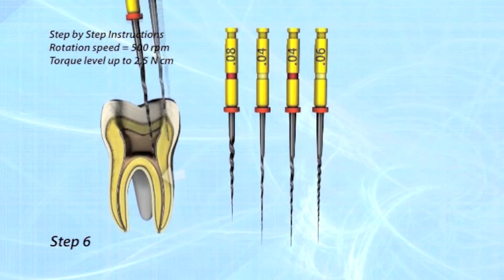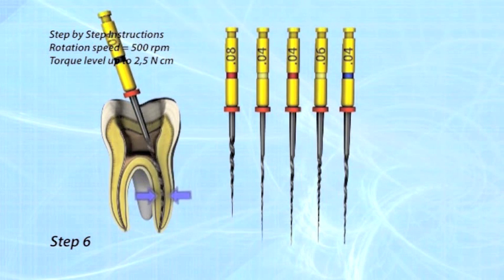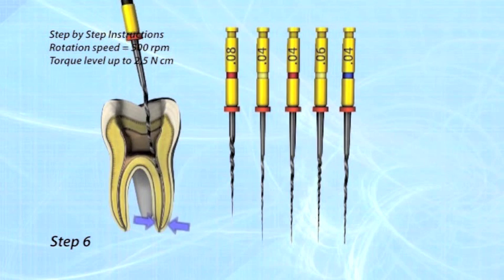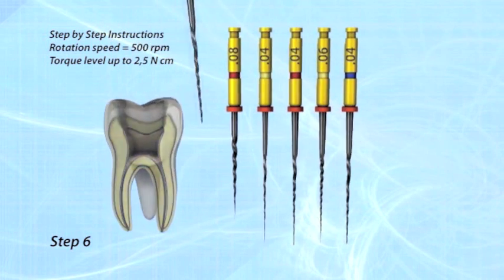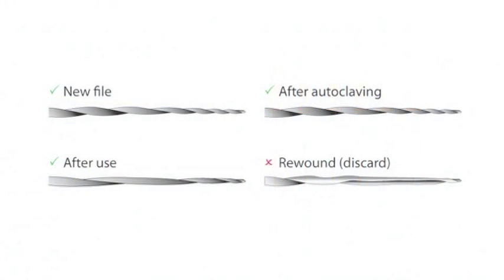Step 6: Finish treatment with the .04 file to working length. If resistance occurs before the working length is reached, go back to the previous step until working length is reached. HiFlex CM NiTi files can be reused as long as they regain their original shape after heat treatment or autoclaving. Files not returning to original shape should be discarded.